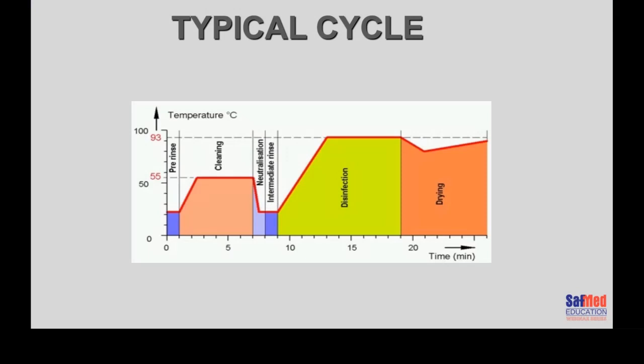Let's look at a typical cycle of the washer disinfector. We'll take all our dirty instruments, load them into the washer, and hit the start button. The cycle depends on which program you choose. But generally speaking, most programs start with the pre-rinse — no detergent, and as you can see, the temperature is a little bit lower. The bar on the side tells you the temperature; the bar on the bottom shows the time. We start with the pre-rinse.